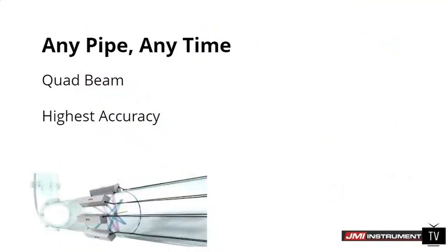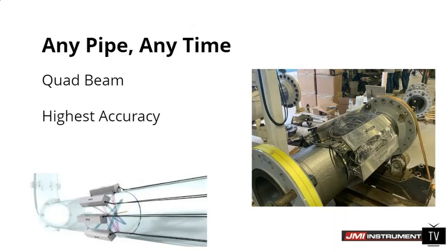This is dual quad beam. So this is something that we do quite a bit on the pipelines, on the bigger pipes. Basically, what that does is the same thing as a dual beam, but we're actually looking at 4 different planes now to get a better profile of the gas going down the pipe. With this type of measurement, we can actually get down to around 0.5% accuracy or error. This is a mock-up here, so we do have some guys that actually put these on spool pieces and get them calibrated at CC or some other lab. And we generally get the highest accuracy from this quad beam, especially in bigger pipes.